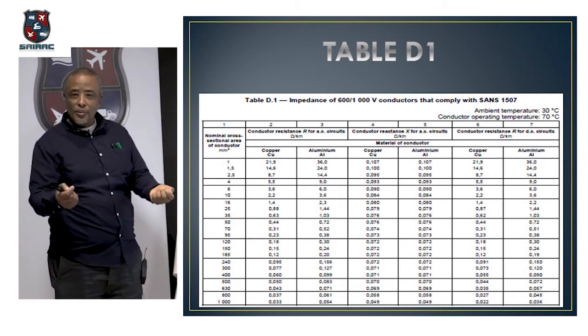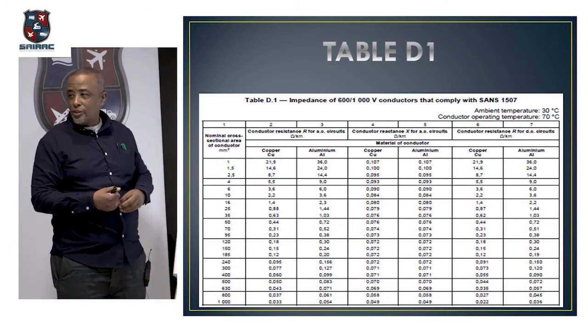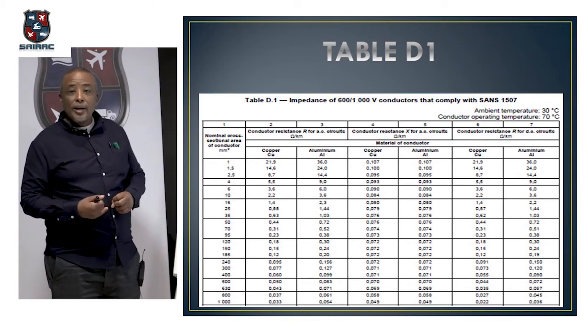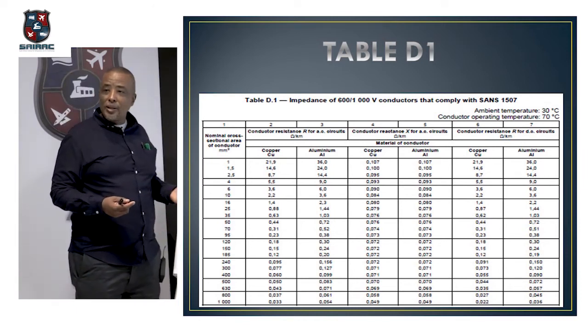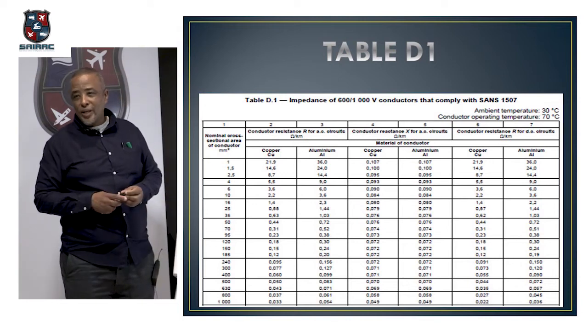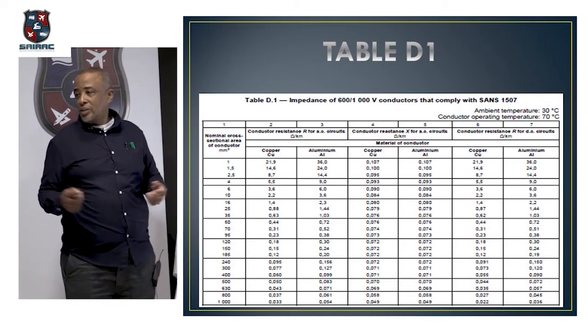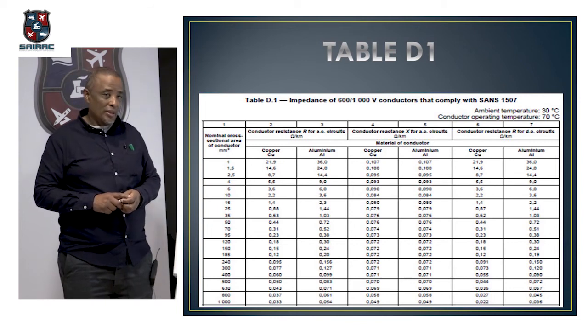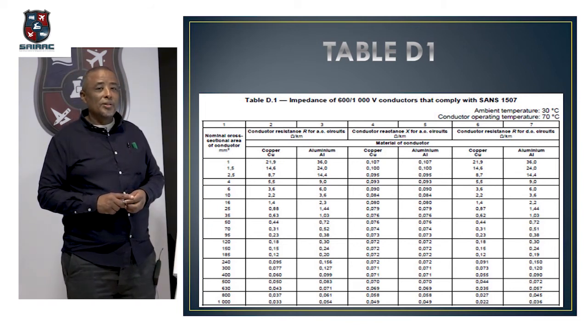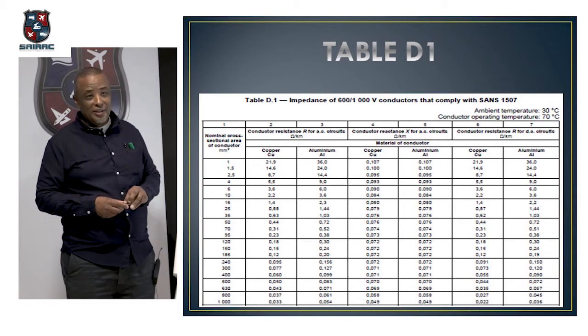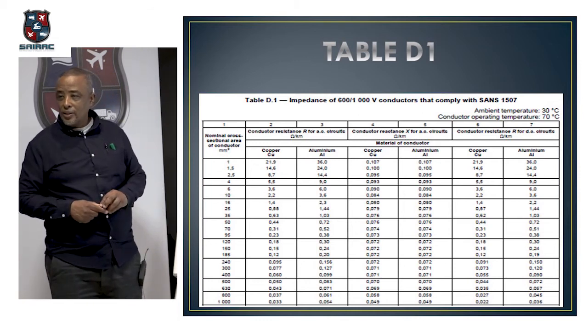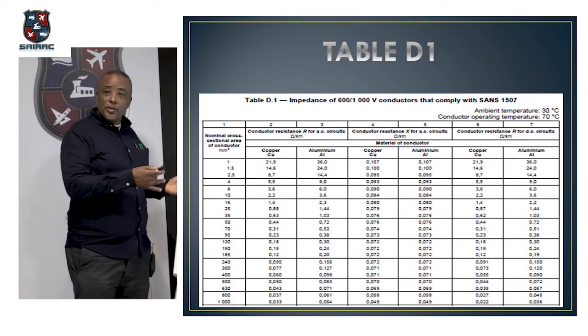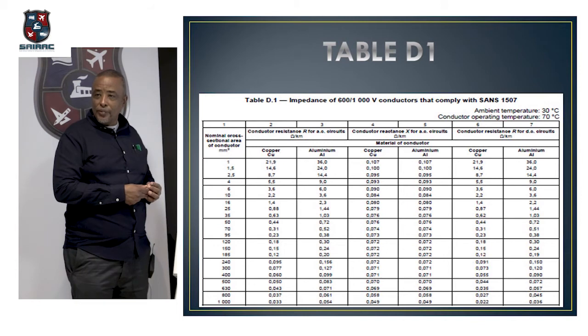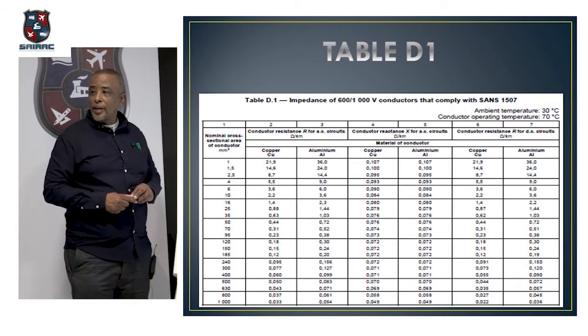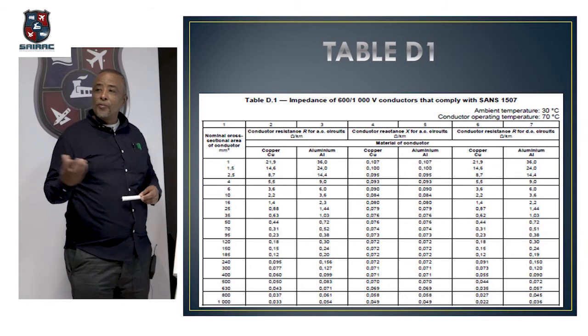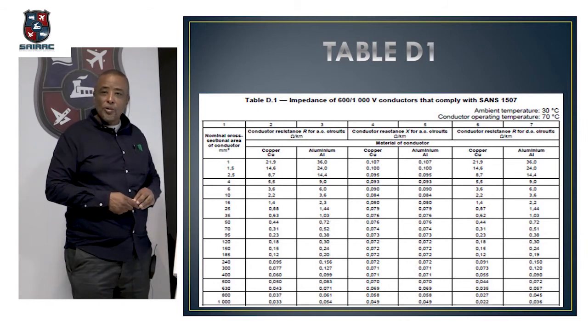If it's under 100 amps, then you can use your meter. It'll be able to tell you what the PSCC is. And based on what the PSCC is, if, for instance, you do your calculation and your reading comes out to, let's say, 7 kA, then your 5 kA is not going to work. So you have to calculate it. Based on that, you will choose what circuit breaker to put in there with the appropriate kA rating. And that obviously goes with cost. So it's very important, don't guess.